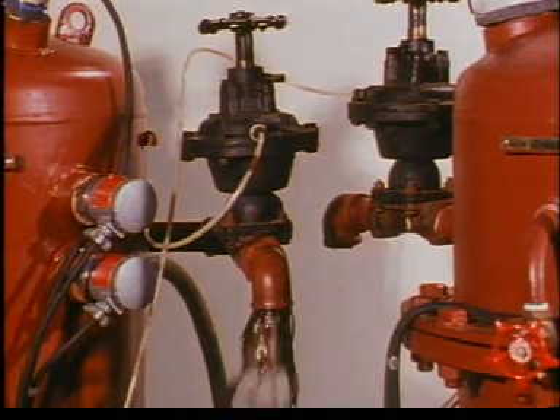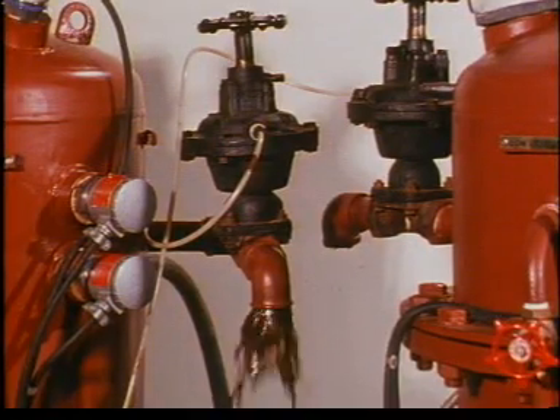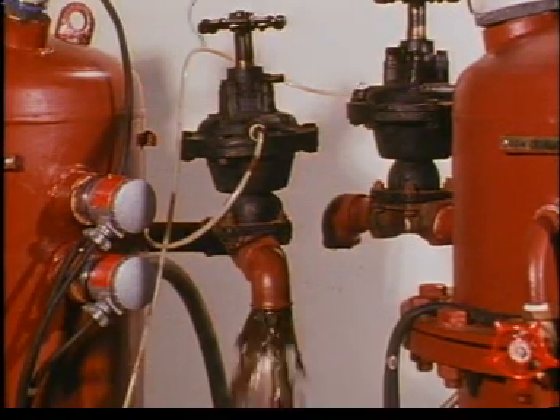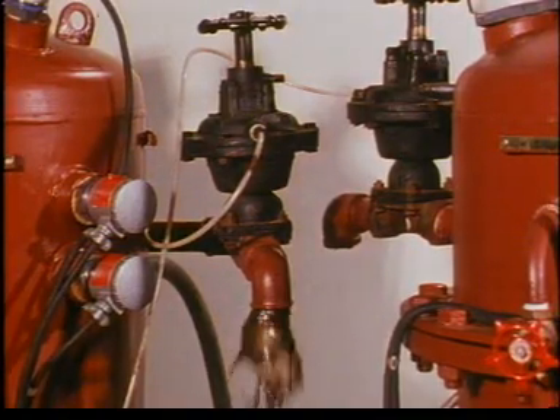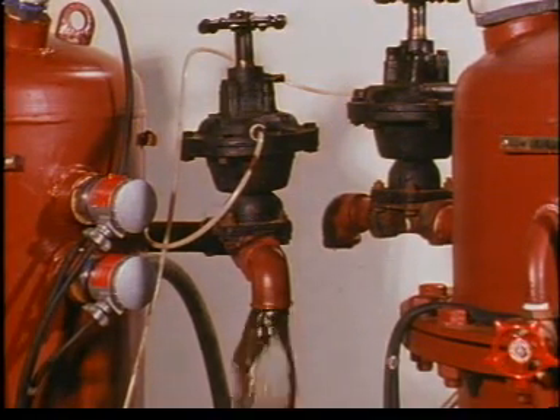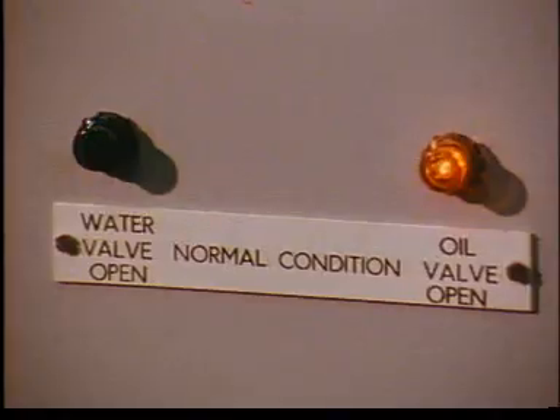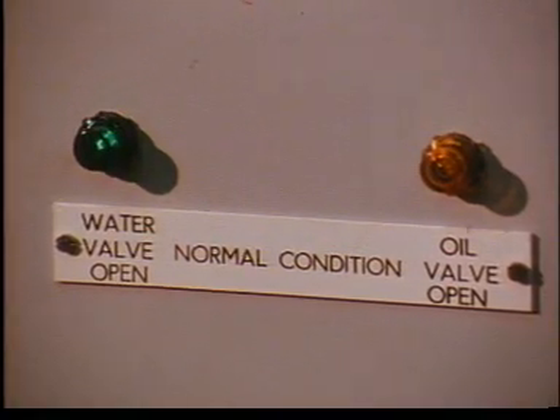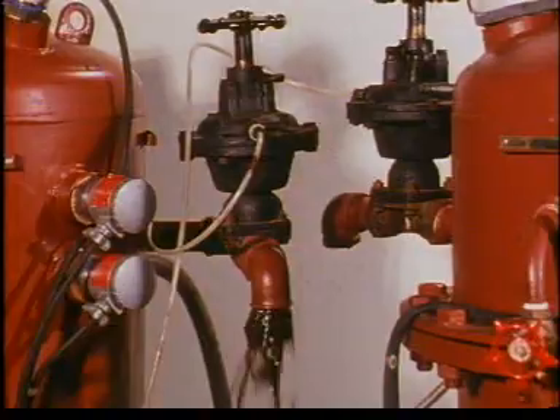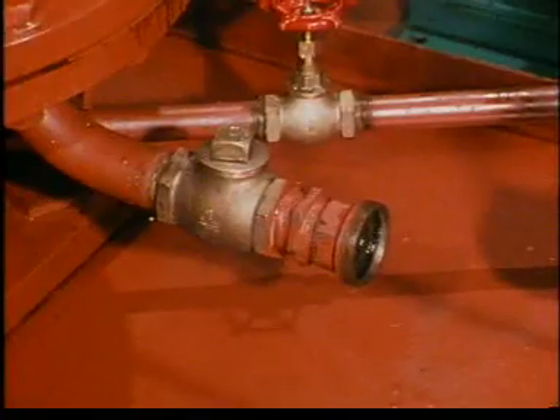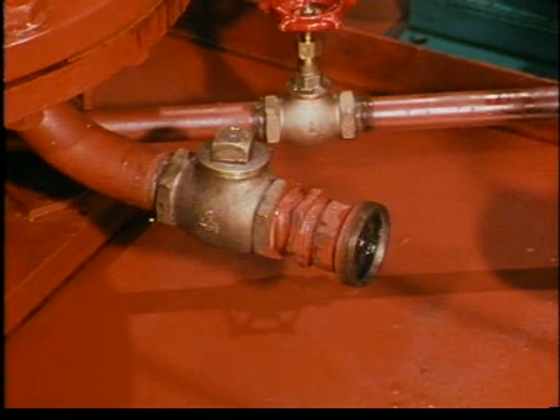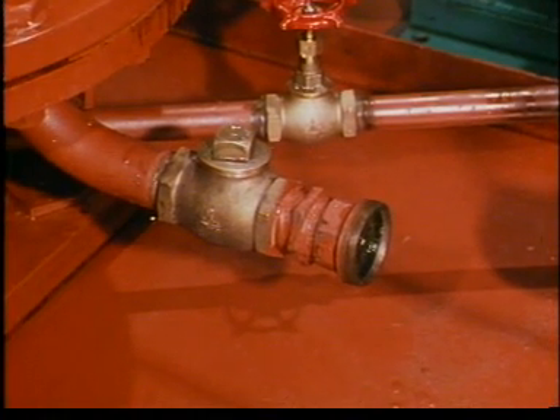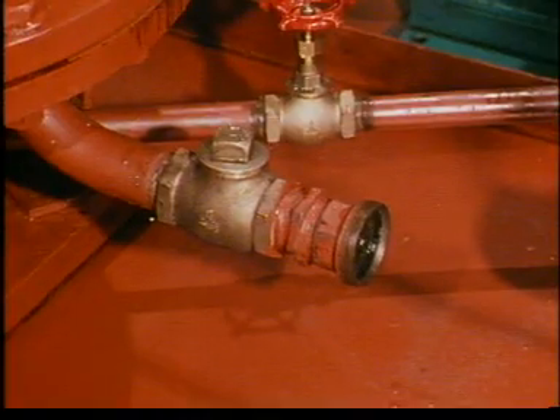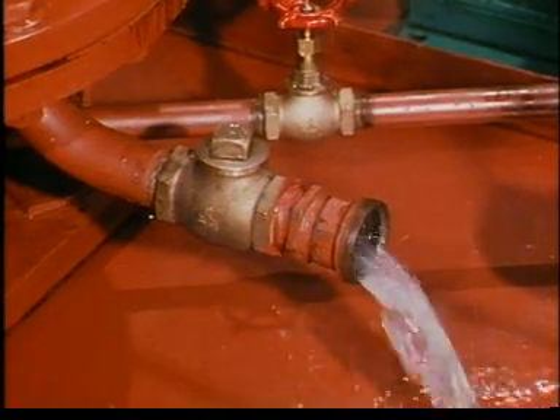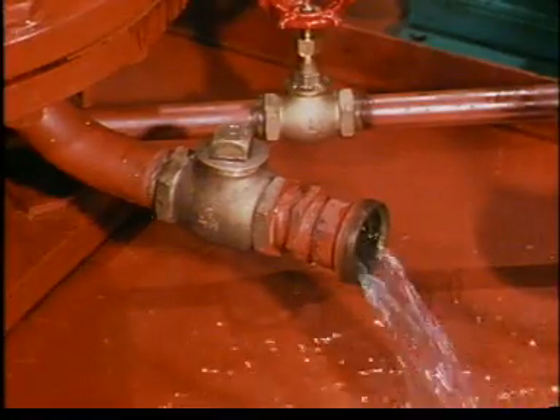For this demonstration, we've removed the pipework so that the outflow of oil is visible. As more and more oil flows out, so the oil-water interface in the separator rises. In due course, the top probe will become immersed in water and the high-level light on the control panel will change from oil to water. When this happens, control air is admitted to the oil outlet valve, which closes. All this time, the water outlet valve is closed, so that pressure now builds up inside the separator, and this causes the water discharge valve, which is spring-loaded, to open, so that the water in the system is discharged.